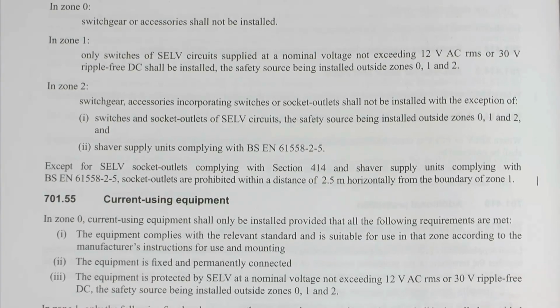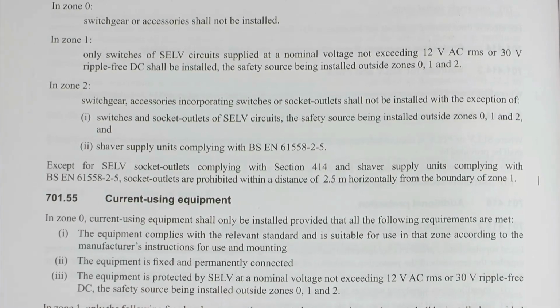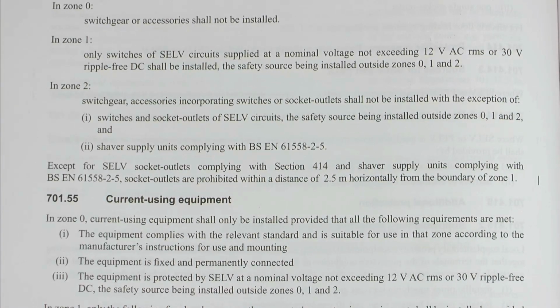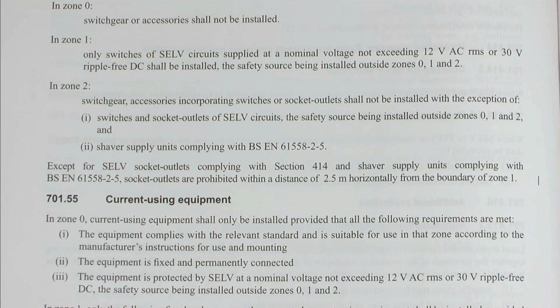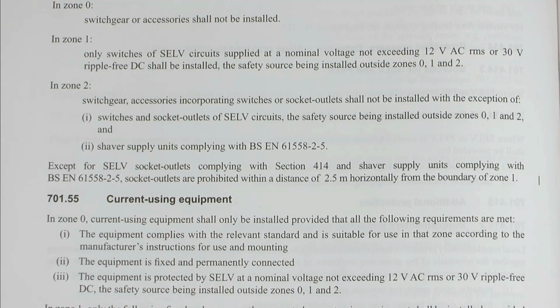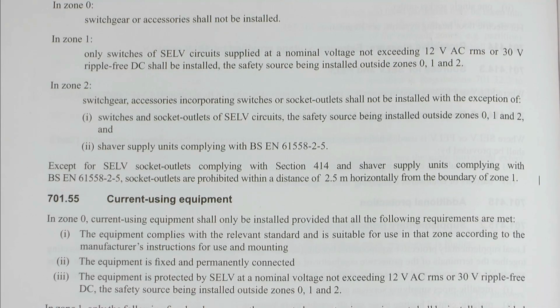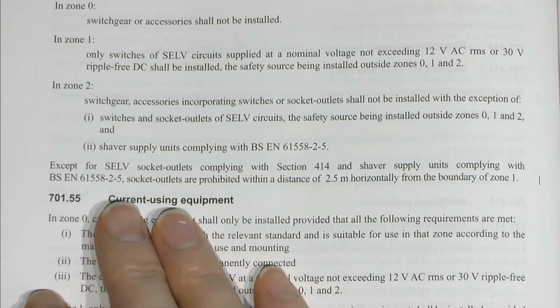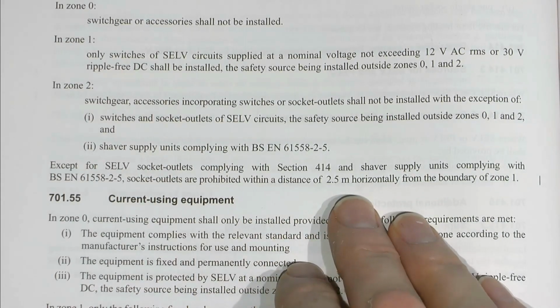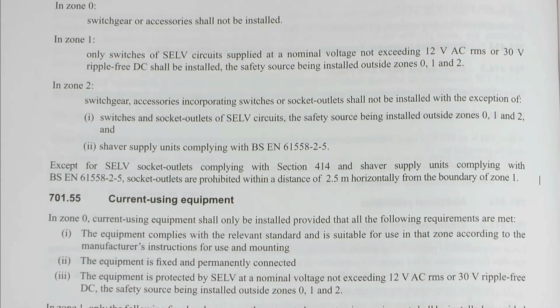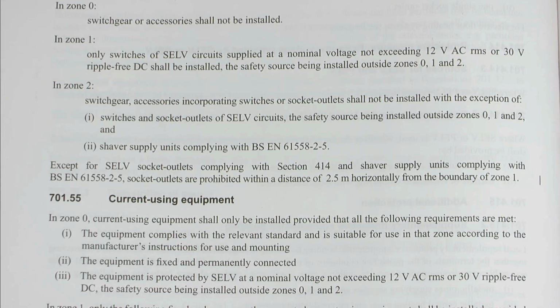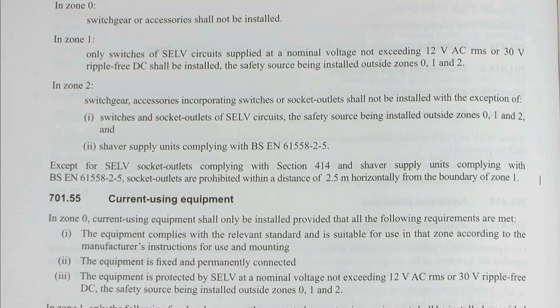Now the next thing here is on the following page, and this is referring to what you can actually install in the various places. Now the actual zones, as in zone 0, 1 and 2, have not changed. Those are exactly the same as they were previously, but what has changed is that for socket outlets, they're now prohibited within a distance of 2.5 metres horizontally from the boundary of zone 1, that's the edge of the bath. Previously this was 3 metres, so now you can have sockets where you couldn't have them before.